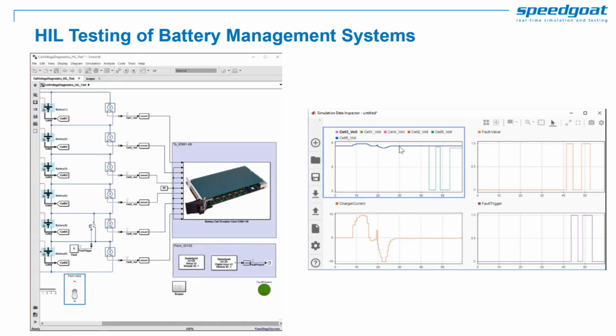We can notice small changes in cell voltages due to change in current, and one of the cell voltages dropped significantly as we trigger the fault, and we can see the corresponding change in the fault status.